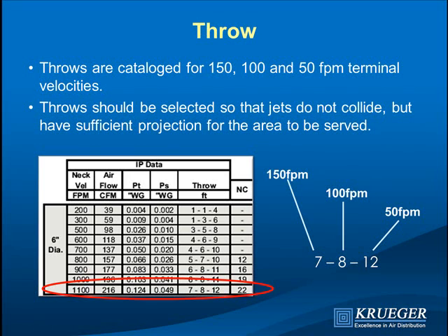Here's our catalog page. We do it in a unique way — we're the only ones that do it this way so we can fit our octave band data on the page. We list air velocities down the side; most people put them across the top. So we've got neck velocity, airflow in CFM, total pressure, static pressure, and three throw values. On the right you see throws at 150, 100, and 50 feet per minute, with a note at the bottom of the page explaining that.